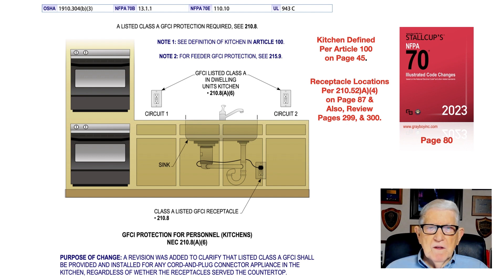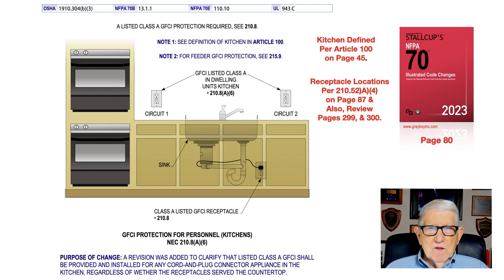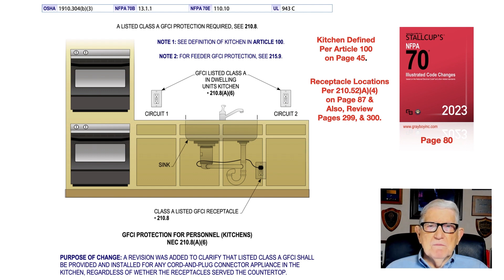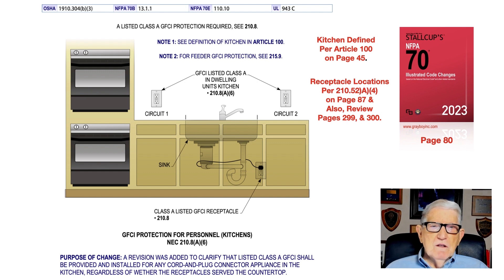This illustration deals with GFCI protection for personnel in the kitchen area. At the top of the illustration, a listed Class A GFCI protection is required in accordance with 210.8 A. Two small appliance circuits are required in the kitchen, with the kitchen definition found in article 100 on page 45.